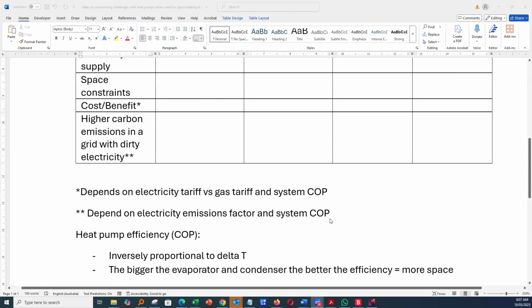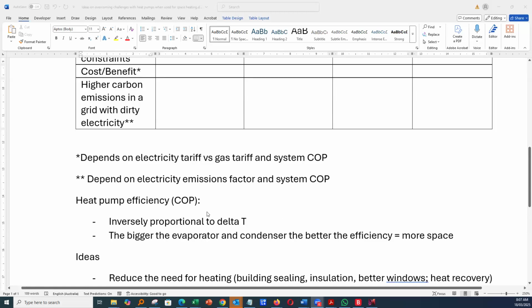Now, just a couple more comments here before I get into some of the ideas. The heat pump efficiency, or COP, is inversely proportional to the delta T. That's the temperature difference between the evaporator and condenser. The bigger that is, the lower the COP, the lower the efficiency of the heat pump. And so clearly, we want to keep the output temperature as low as possible in order to get a higher COP. The higher we go, the worse the COP.